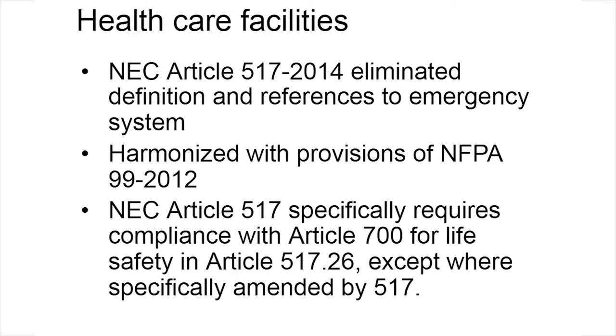The 2015 NFPA 99, the Healthcare Facilities Code, says that those fire protection requirements don't apply to hospitals. And let me repeat that. The 2015 version of NFPA 99 specifically exempts hospitals from fire protection requirements for feeders. The 2017 NEC specifically adds hospitals to the fire protection for feeders, and Article 517 does not address it.